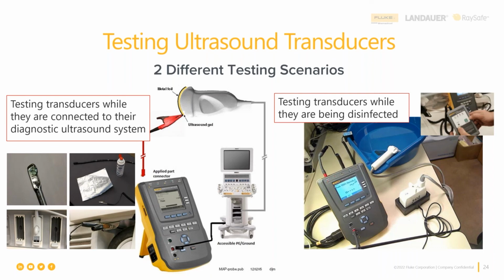Well, who does that testing? Is Biomed doing that testing and cleaning? No, it's central processing or the sonographer, depending on the location, a clinic or a hospital. These people are less technical than we biomeds, less well-trained technically. So we provide the ULT 800, which allows a pass-fail with a battery-powered device to keep the cleaning technician or sonographer safe if they put their hands in the cleaning solution during the testing, because it is a mains on applied part kind of a test to test lead isolation.